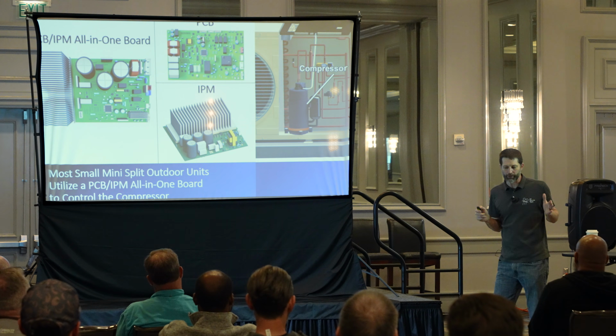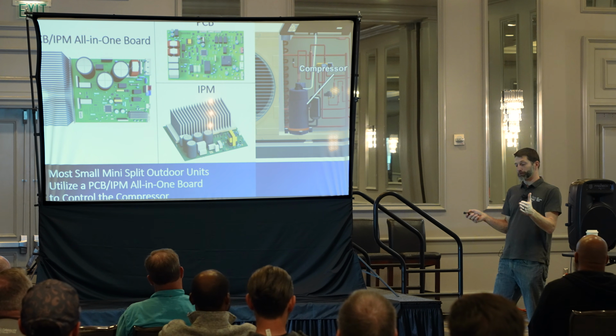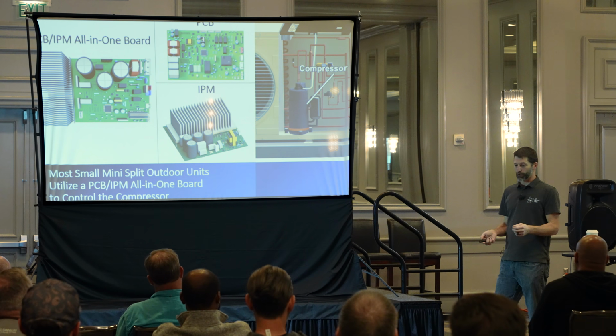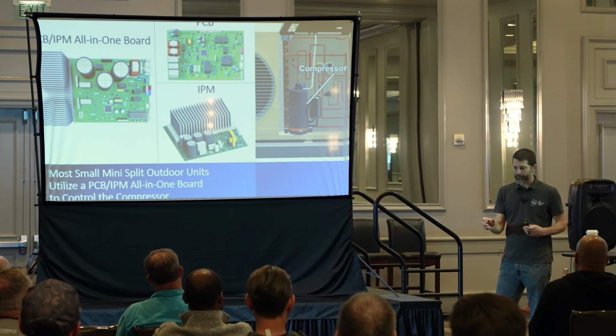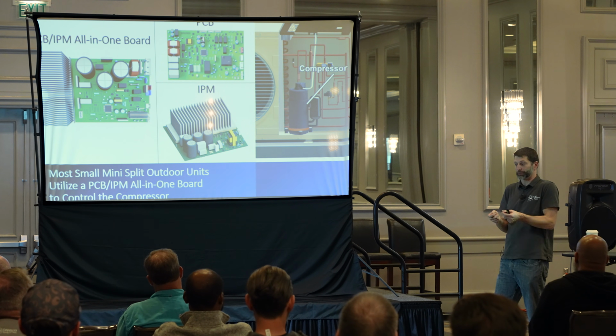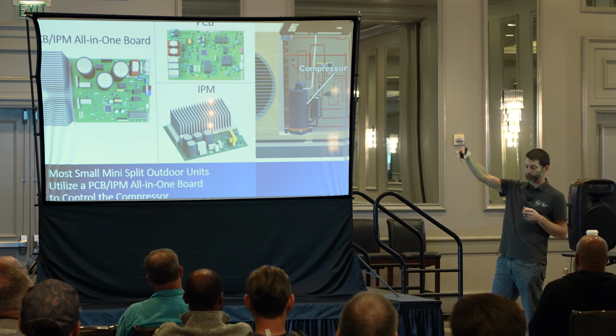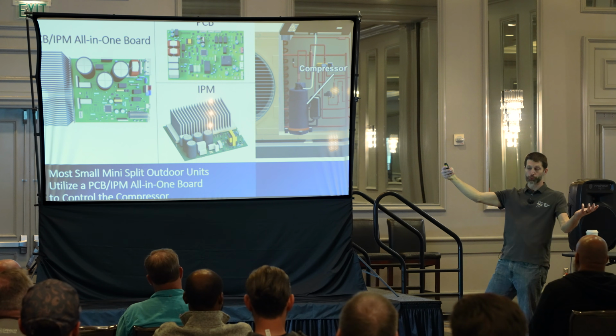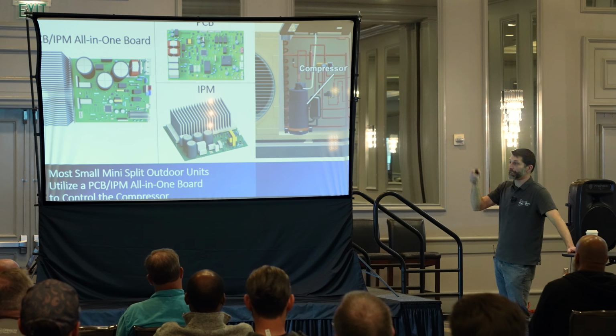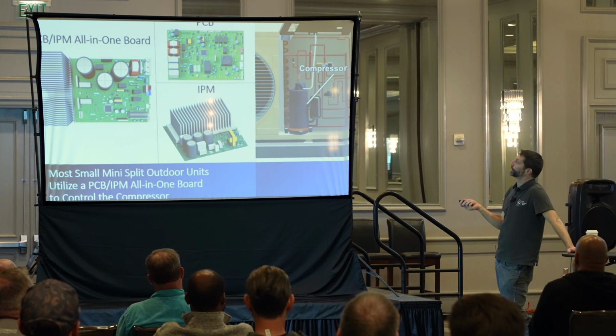It's very easy to determine if a three-phase wound compressor is intact. As long as it's not mechanically seized, electrically you're just checking that the resistance matches on every single pair, and that there's no continuity between the three wires and ground, so it's not shorted. Same thing with the EEV, you can check the electrical resistance. We're going to get into all that stuff.